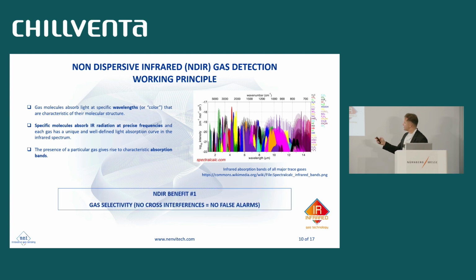So each gas has a specific absorption band in the infrared spectrum. And from this property derives a first great benefit of infrared technologies, which is gas selectivity. So we can be sure, if we have attenuation at that specific wavelength, that we have presence of that specific gas. And if there are other gases, those will operate in other areas of the spectrum, and therefore we will have no cross interference from those other gases or chemicals. And that means no false alarms. The sensor will react to the refrigerant gas and only to the refrigerant gas.